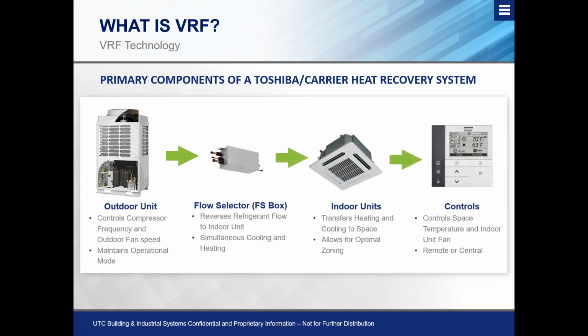Okay, now we talk about the Toshiba Carrier heat recovery system, and we look at this as an outdoor unit, an indoor unit, some form of control. And just like on the two-pipe or the Carrier system, the Toshiba Carrier system has the FS box, just like I talked about before, except now we're not calling it an MDC, we're calling it a flow selector, but it is essentially doing the same thing. It's governing that refrigerant control and how it's actually going to the indoor units. So it's like a governor in the system. If the system doesn't need refrigerant, the solenoid valves aren't going to open up. If it does need heating, a temperature call for heat or for cooling, it's going to open up the appropriate valves, whether that be hot gas, liquid, or suction. Essentially they're doing the same thing, and that is the crucial piece of a VRF heat recovery system that allows you to simultaneously heat and cool without a conflict. But essentially, we're working with the same thing.